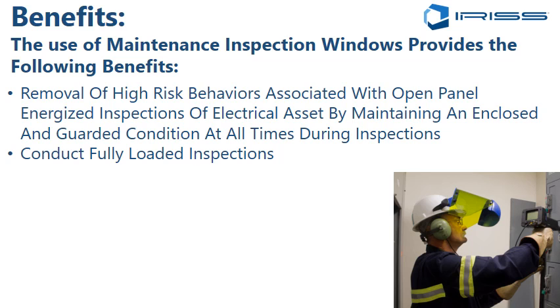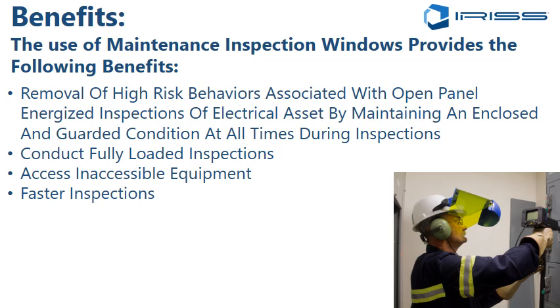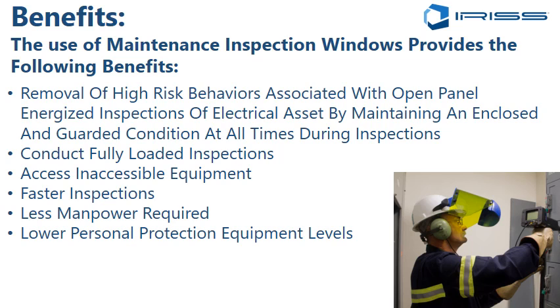They enable us to do fully loaded inspections in line with standards like NFPA 70E, which require a minimum of 40% load at any time. Condition monitoring of equipment really needs to be done under a loaded condition, otherwise it doesn't have any value. They enable us to access inaccessible equipment because the panels remain closed. There's no trigger of an arc flash, and you're not standing in front of energized equipment, so everything becomes accessible. The inspections are much faster, with much less manpower required. One person can do this because you haven't got 2 people removing covers. There are also lower personal protection equipment levels, because the panel is in a closed condition, so the arc flash levels are not elevated, nor are there PPE requirements.